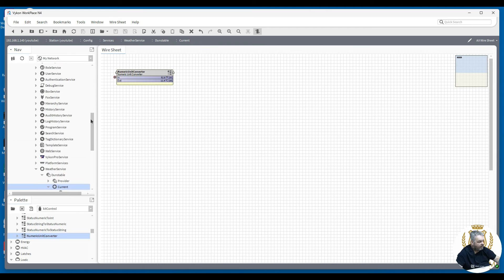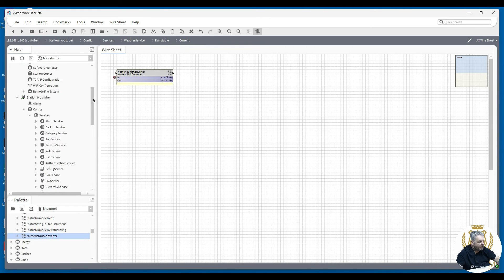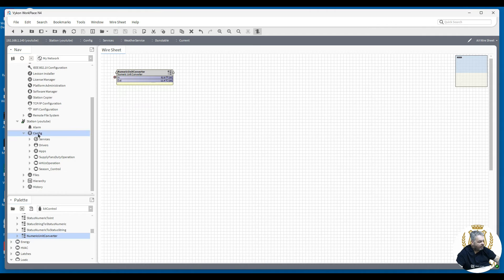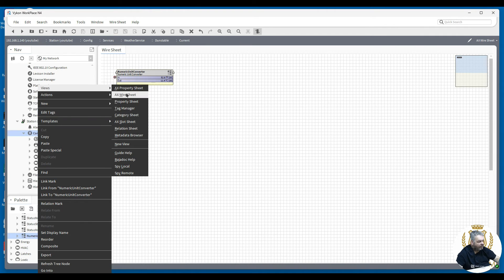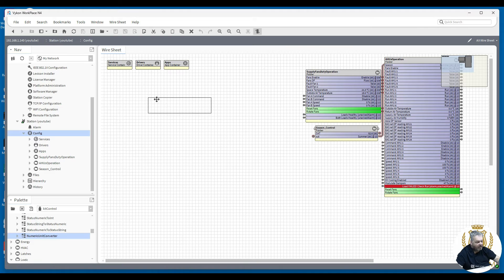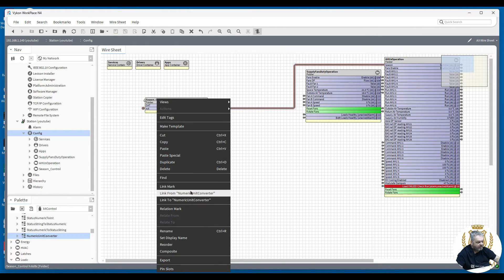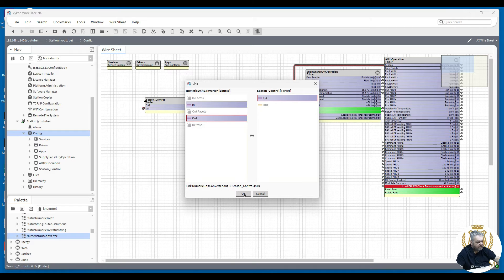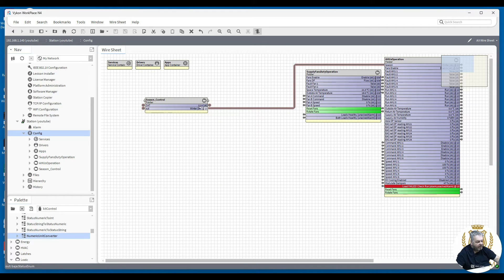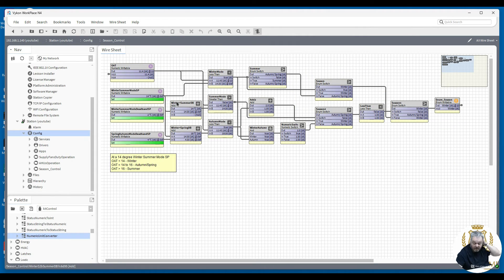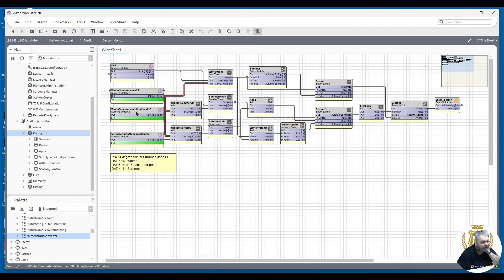Then all you need to do is link that out to your logic. If you're using something like the season control, link from the output into there — that's telling you the temperature, and the season control folder has now gone to winter. The logic is easy enough to write. You've got your outside air temperature coming in, a setpoint for winter/summer mode, a dead band, and a spring/autumn dead band.